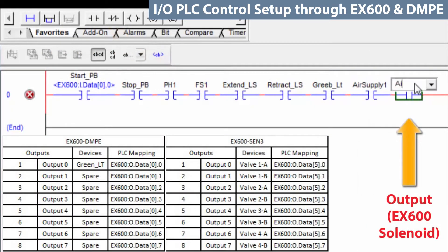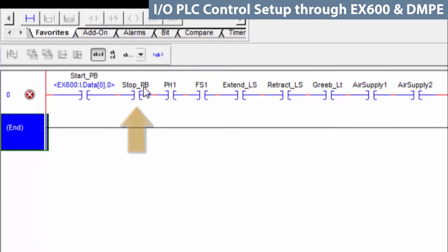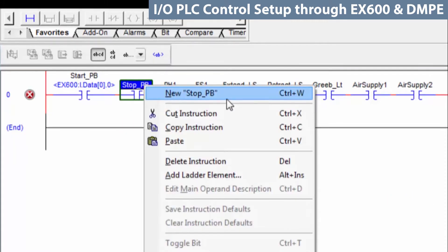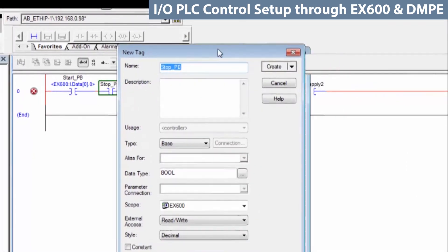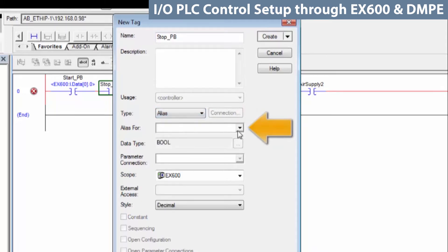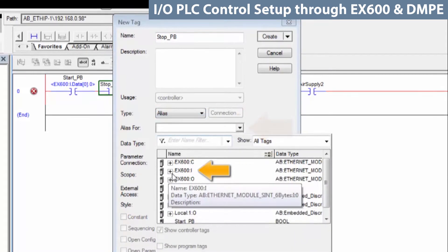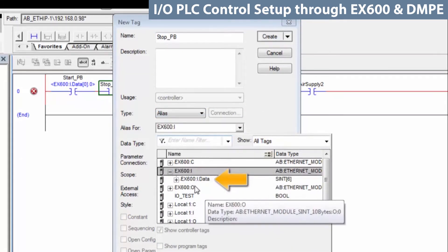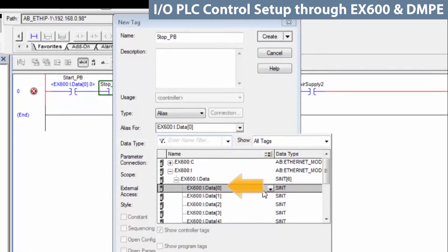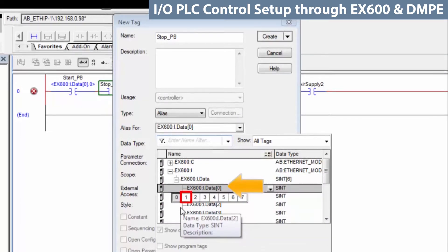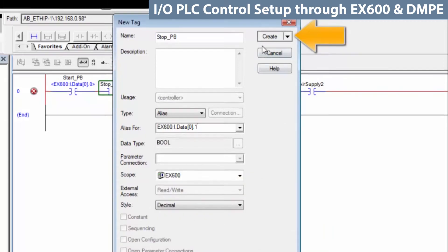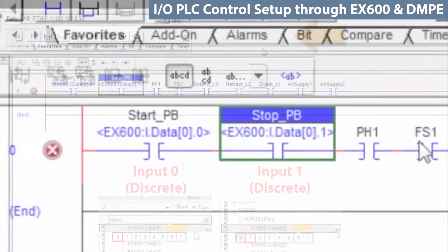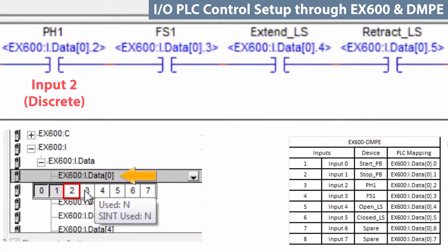Then, add the inputs. So, right-click on the stop, create new, and under this tab, tell it to create an alias for that. Go to the pull-down and read EX600 inputs, data, byte 0, and notice that bit 0 is grayed out because it is already associated with the start push button. Select bit 1 and create. Now, we can see that the stop push button was added to the rung just like the start push button. Do the same thing with the photo-eye.